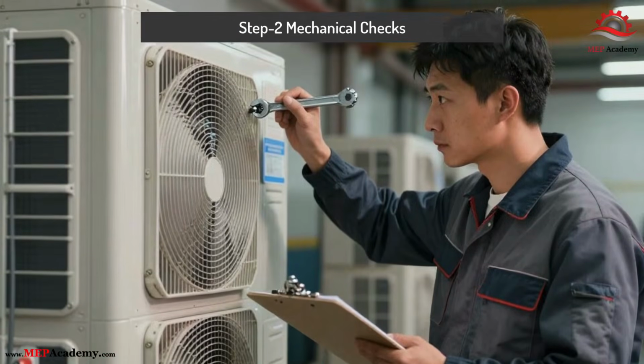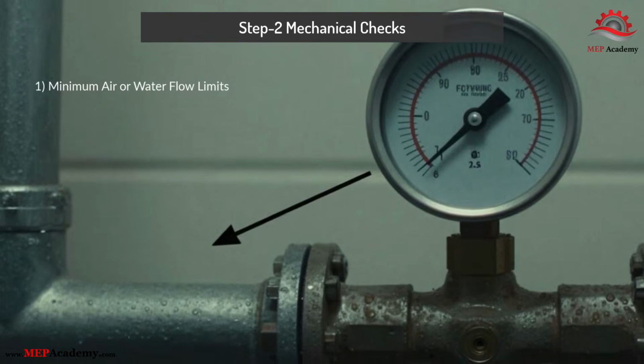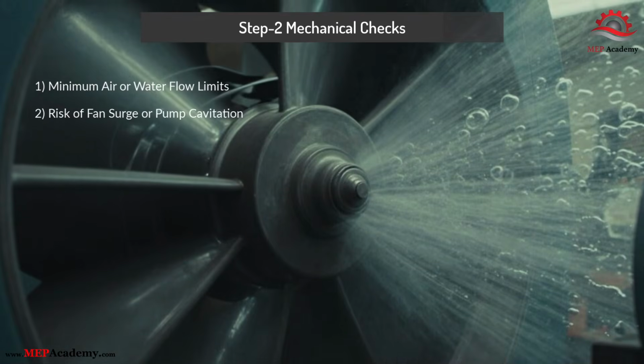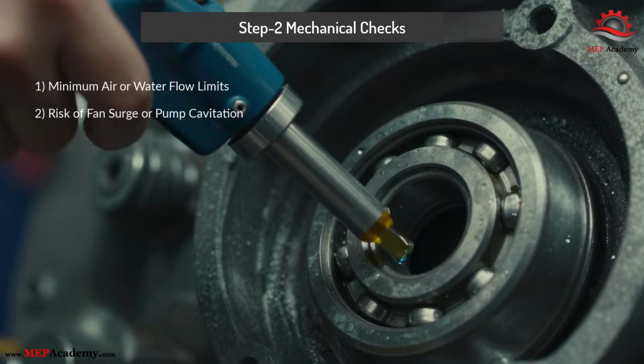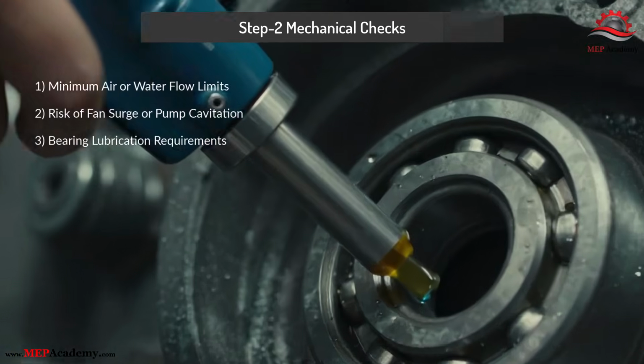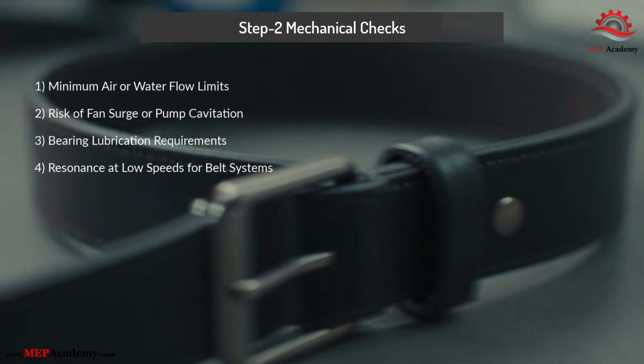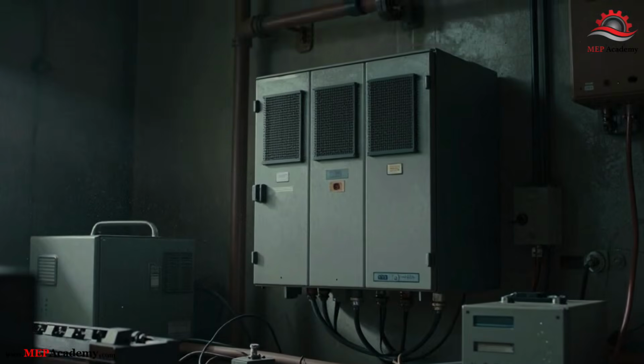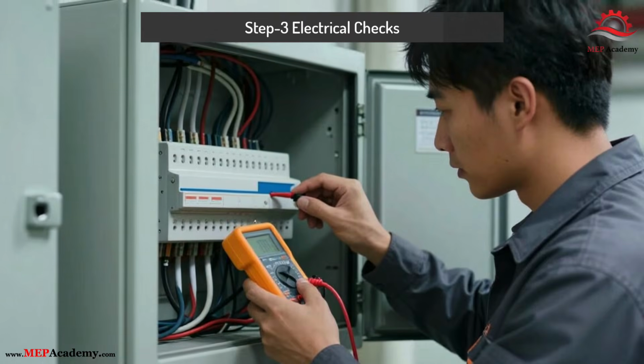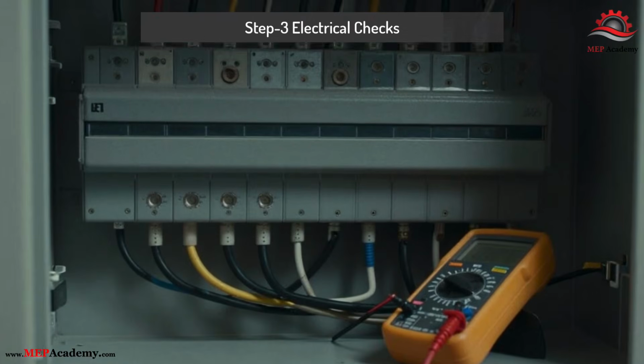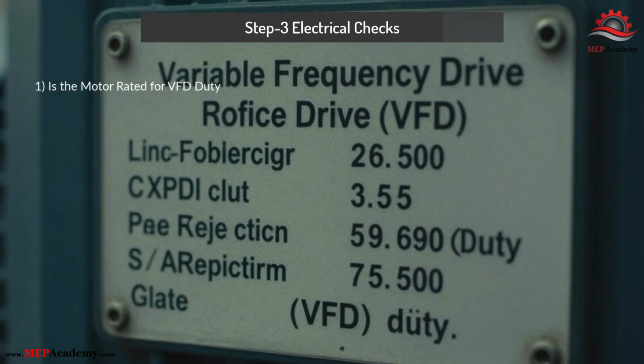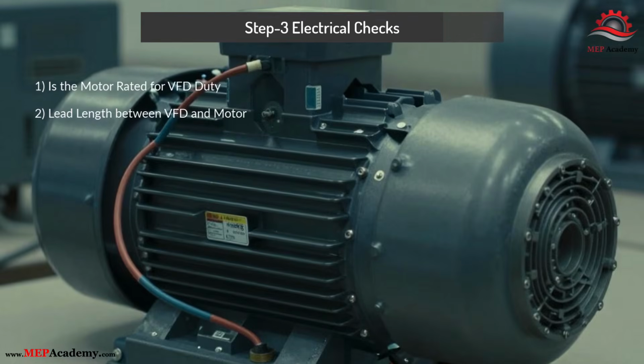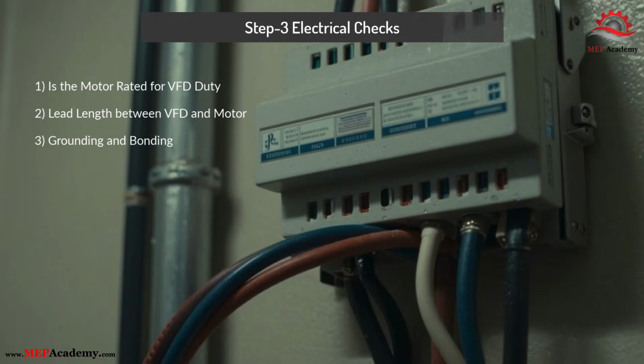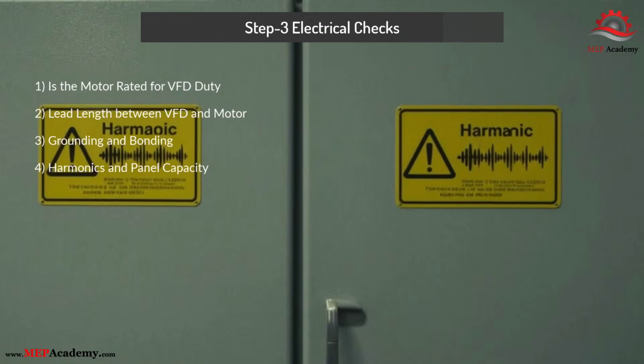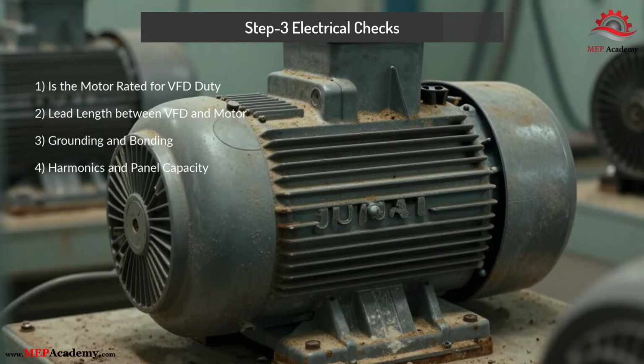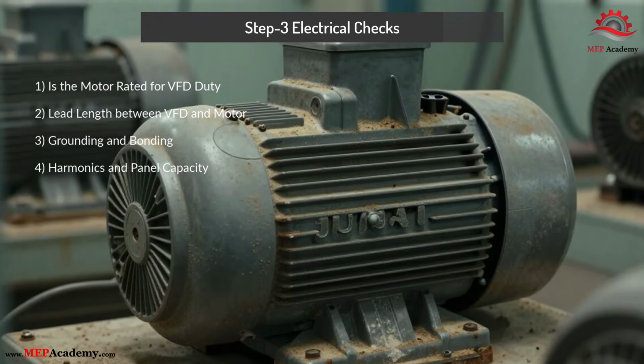Step 2. Mechanical checks. You must confirm minimum air or water flow limits, risk of fan surge or pump cavitation, bearing lubrication requirements, resonance at low speeds for belt systems. This is where many retrofits quietly fail. Step 3. Electrical checks. Electrically, you need to evaluate: Is the motor rated for VFD duty? Lead length between VFD and motor. Grounding and bonding. Harmonics and panel capacity. Older motors can often survive VFDs, but not always, and not without risk.